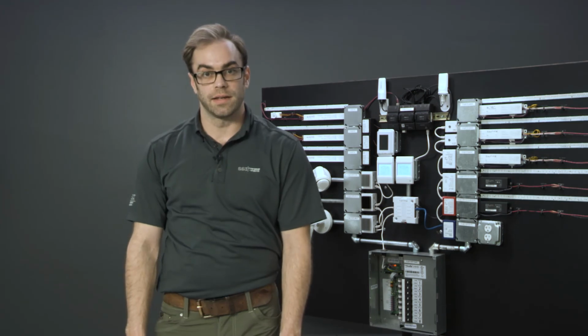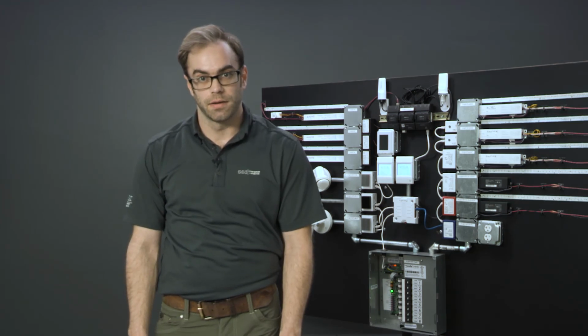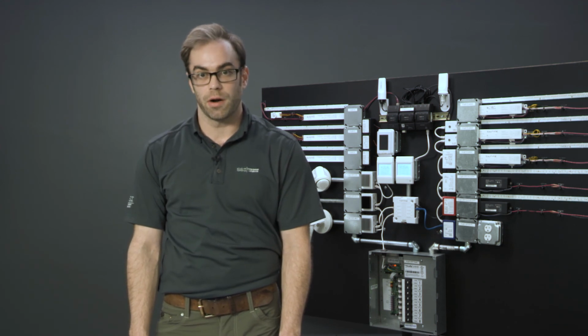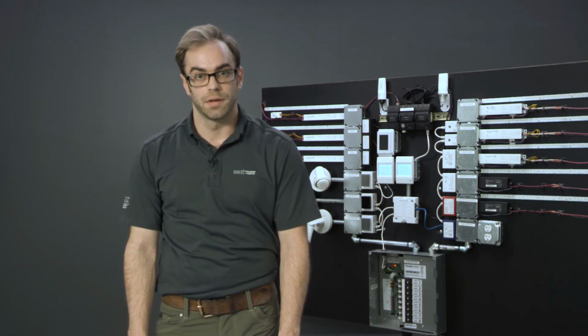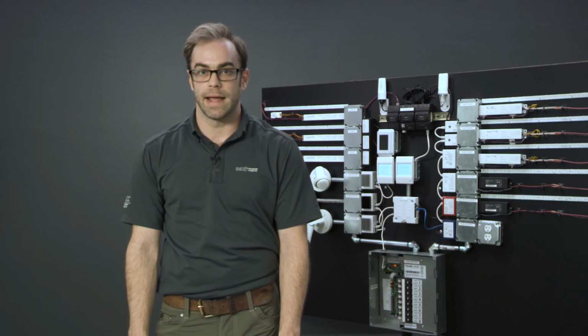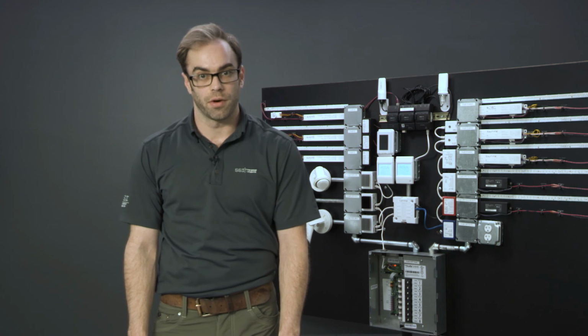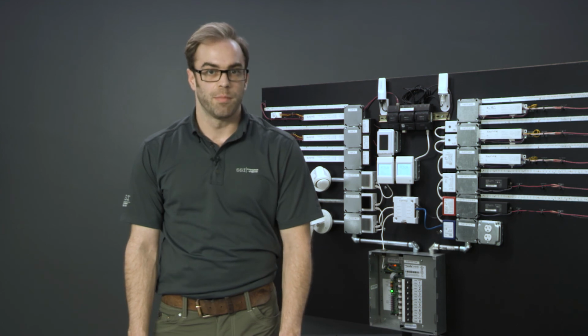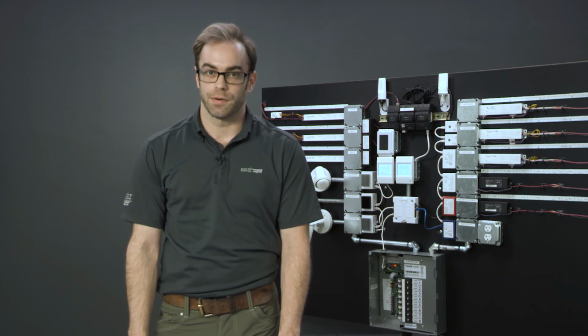Let's return now to the idea of out-of-the-box functionality. As we've discussed, an nLight zone consisting of 2 switches and 2 power packs would behave as follows. Switch A and switch B would both toggle power packs A and B until separated through programming. But now let's introduce an nLight bridge. Each port off of an nLight bridge behaves as its own separate nLight zone.